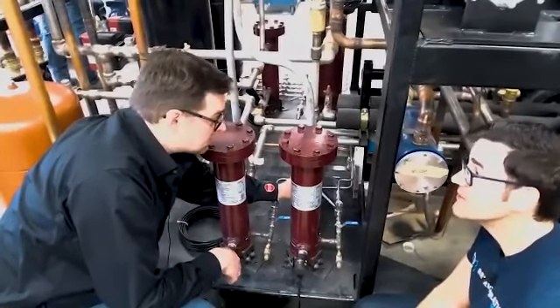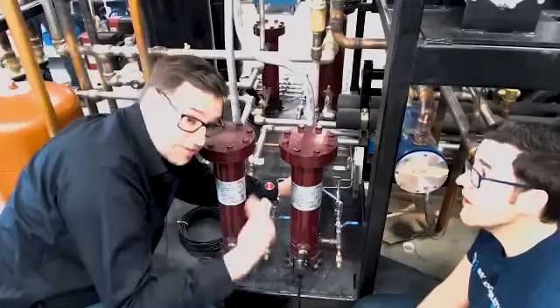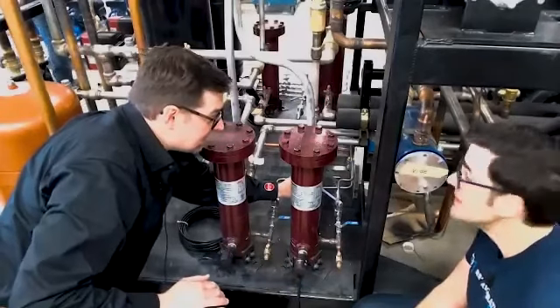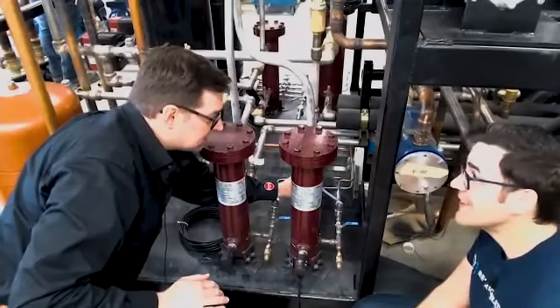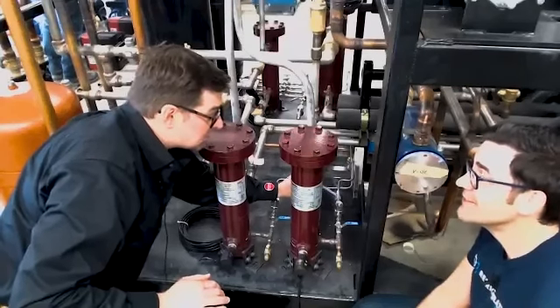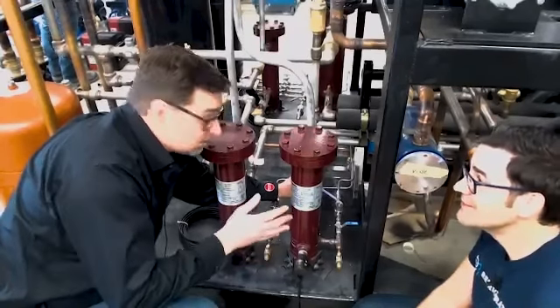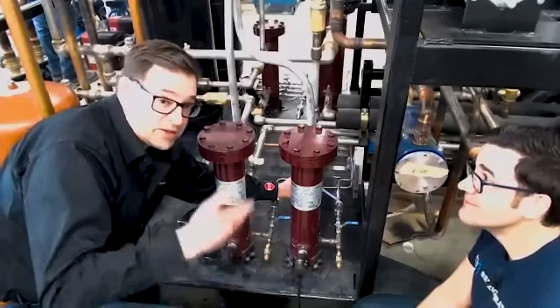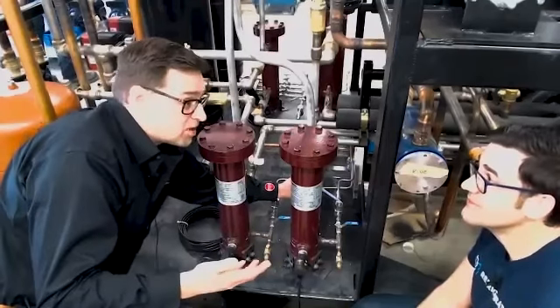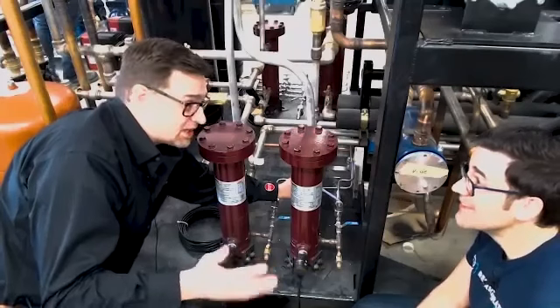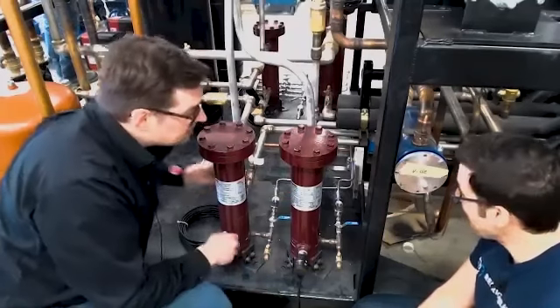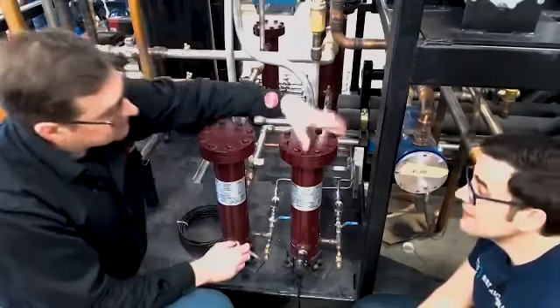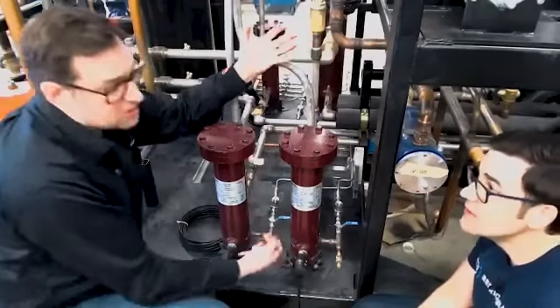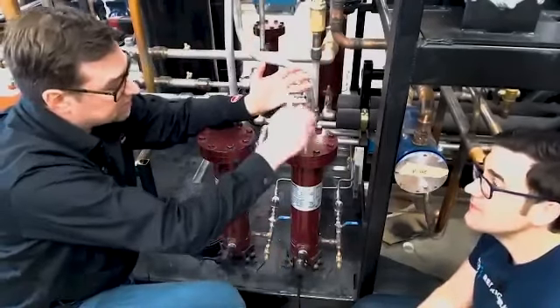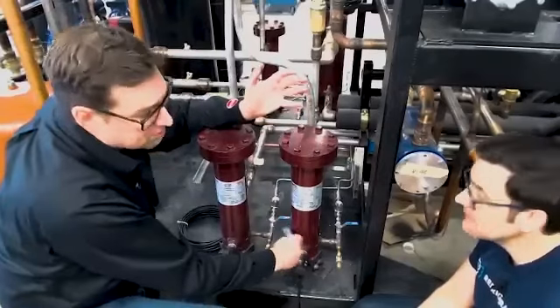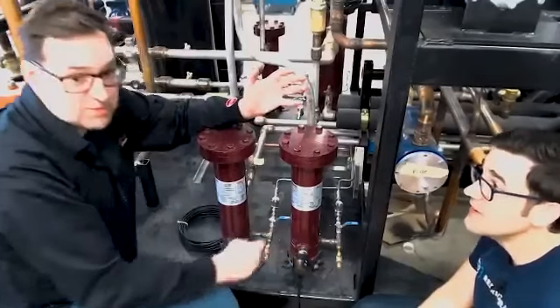At startup, we ship a 15 micron with it to get all the particulate debris out, and then after startup we'll put a 40 micron in. This is the first stop to removing a lot of that debris that's filtering through the system just because of all the work that was done on the system. This is common debris that's going to circulate, right? Another interesting thing is a lot of the time we'll take the head off and clean the inside of the oil separator. If you take a good look, not just the filter, after the startup you could have some debris inside here that needs to be removed as well.